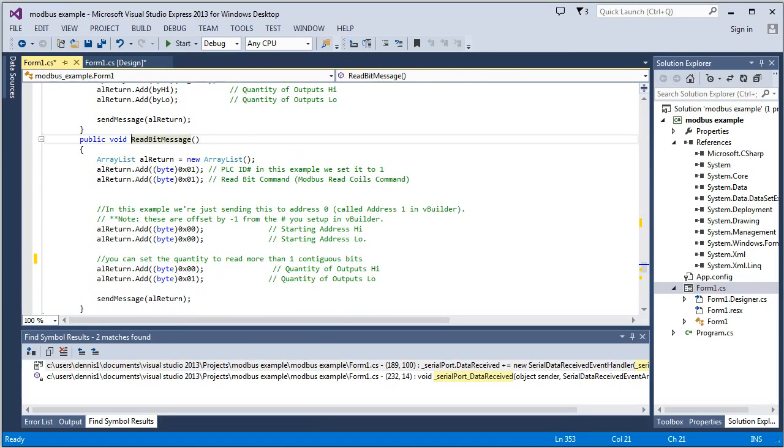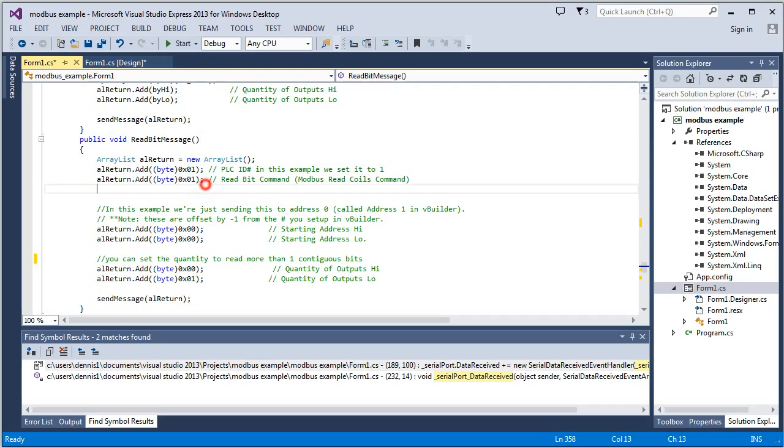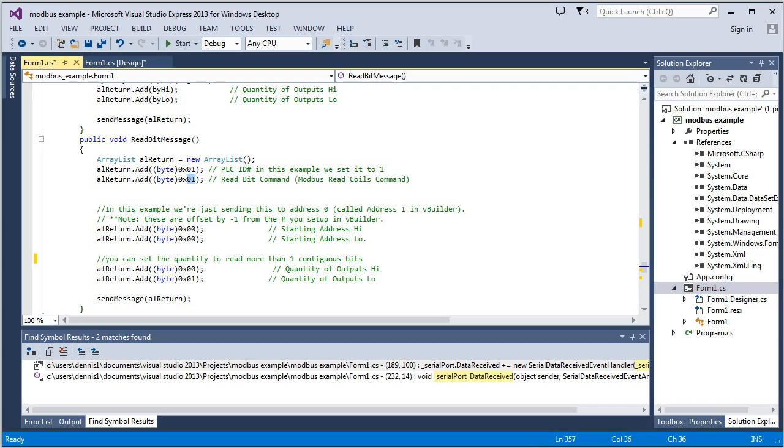And it's the same PLC ID. And we're sticking with the default there. And the command is different. It's a 01, which reads a bit or what Modbus calls read coil command.